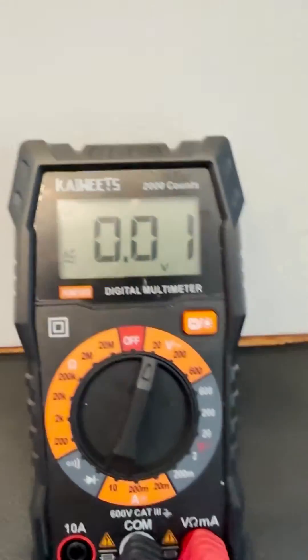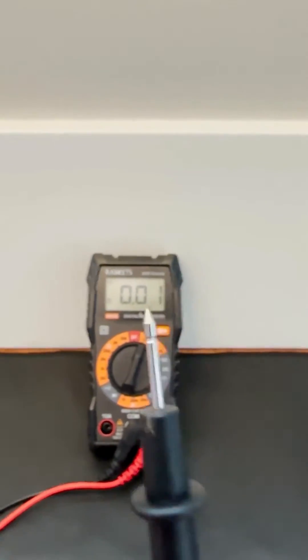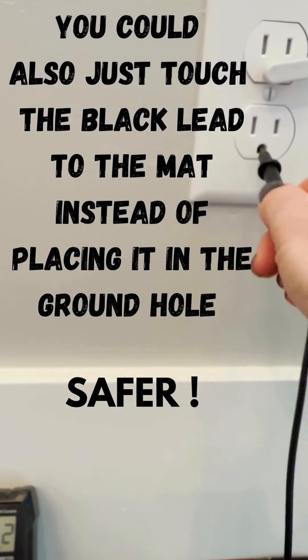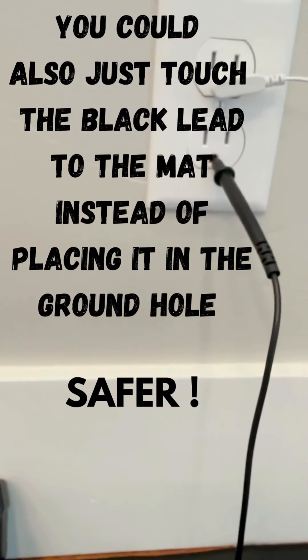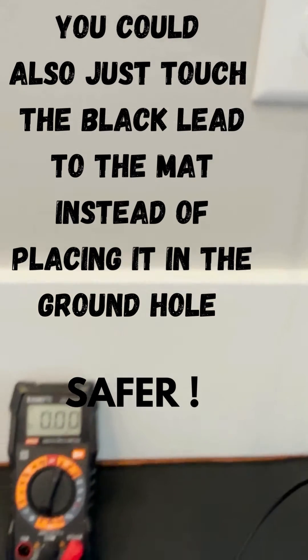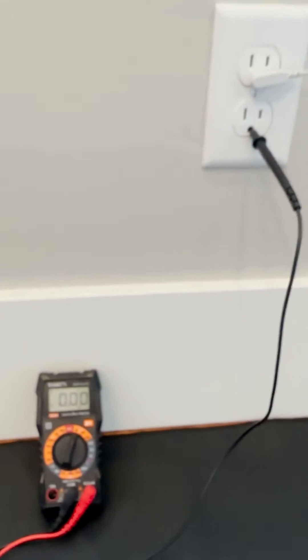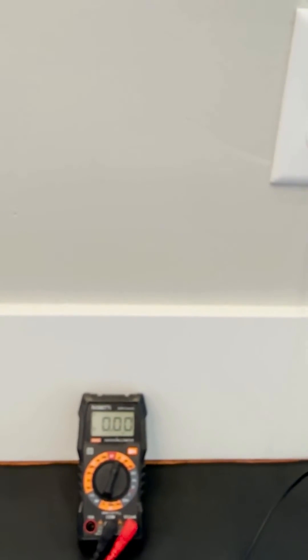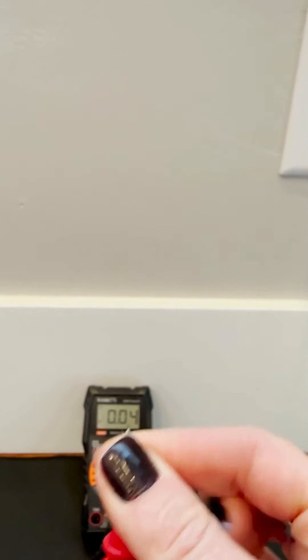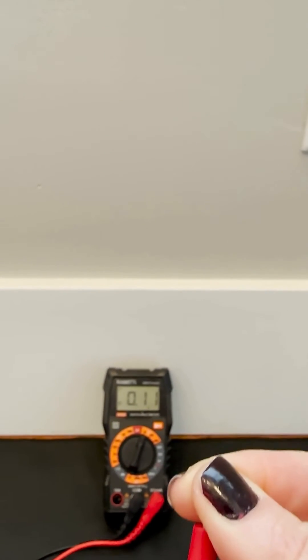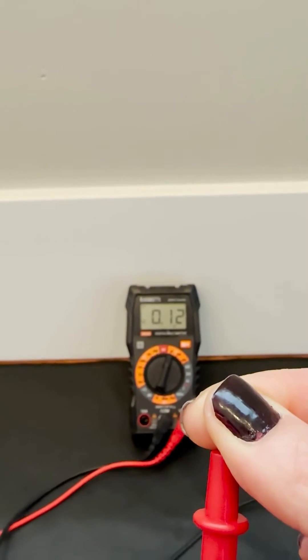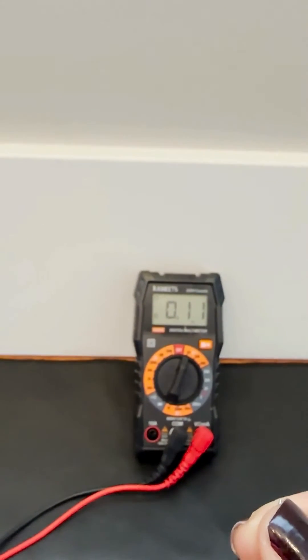I am going to take the black lead and put it into the ground hole of the outlet. Sometimes it stays, sometimes it doesn't. You'll see I have zero reading on the multimeter. I have the black lead in the ground port. I'm going to pick up the red lead in my free hand and hold on to the end of the probe. You're going to see I have a reading now on my multimeter.